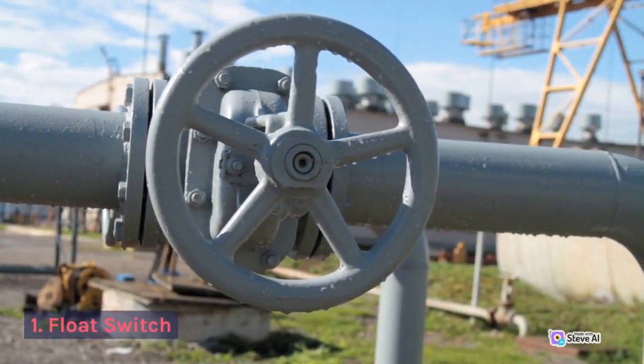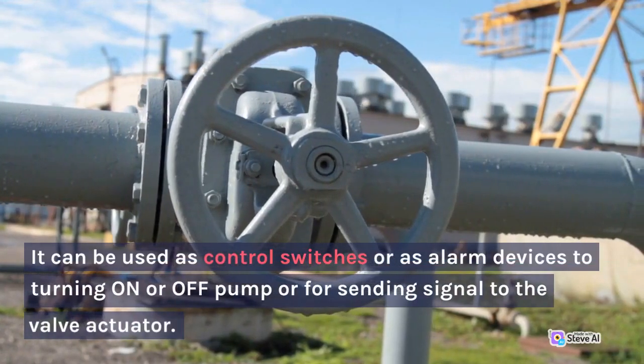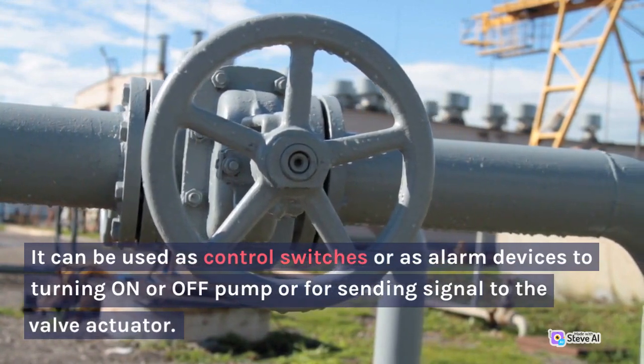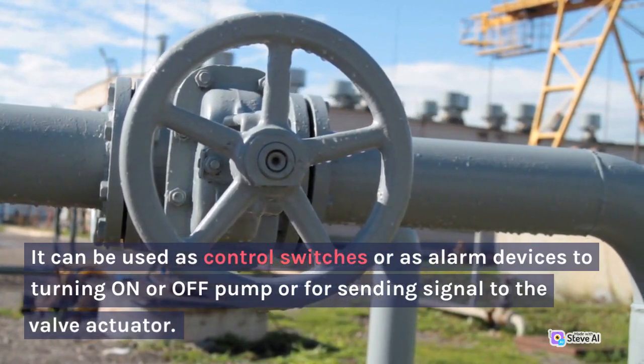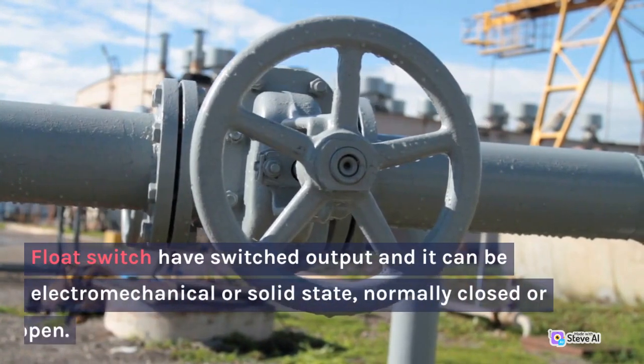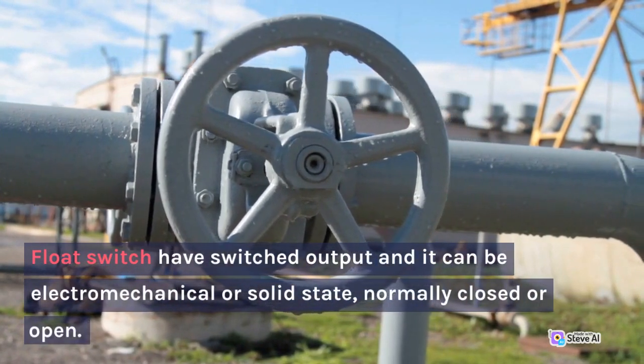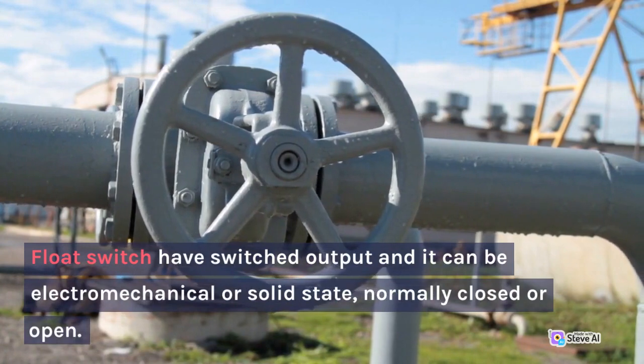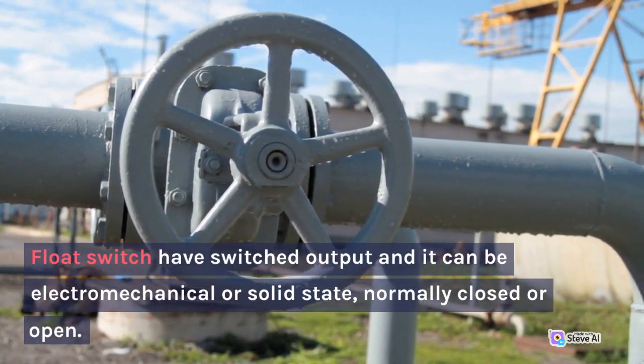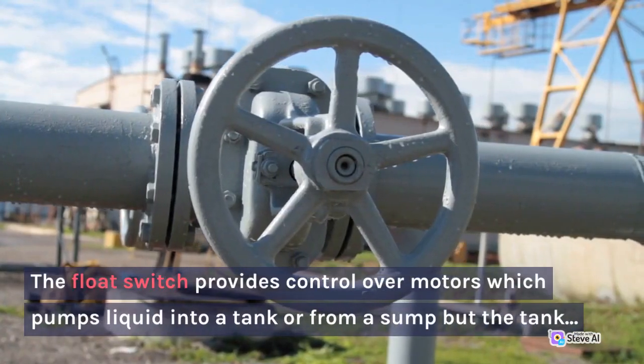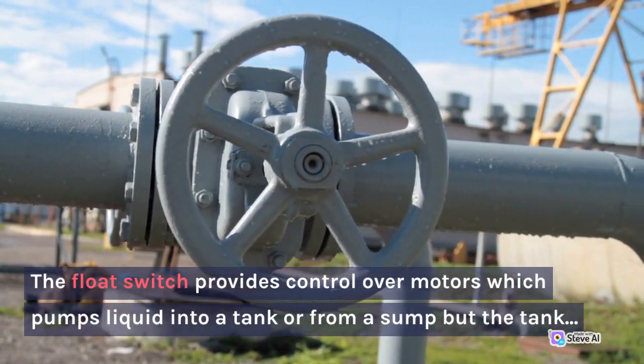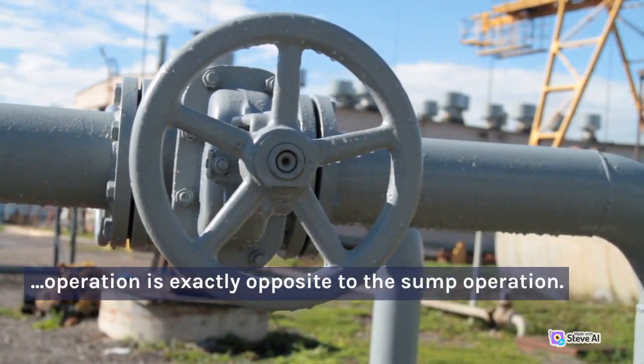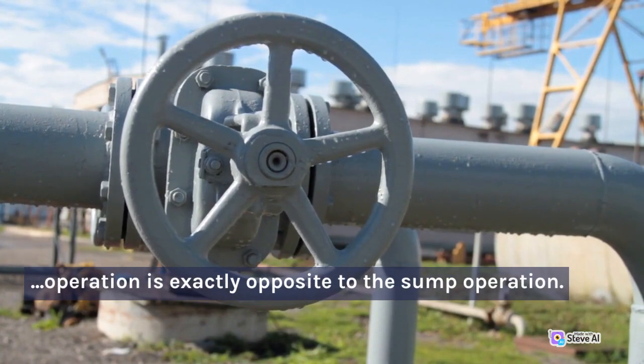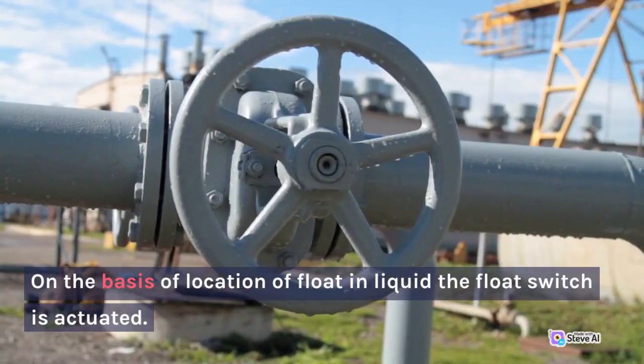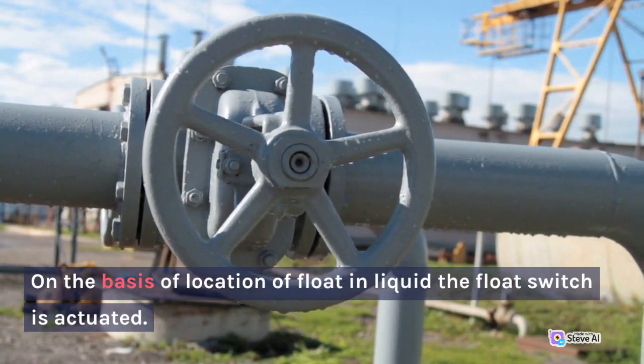1. Float switch. It can be used as a control switch or as an alarm device for turning a pump on or off or for sending a signal to the valve actuator. Float switches have switched output, and can be electromechanical or solid state, normally closed or open. The float switch provides control over motors which pump liquid into a tank or from a sump, but the tank operation is exactly opposite to the sump operation. On the basis of location of float in liquid, the float switch is actuated.